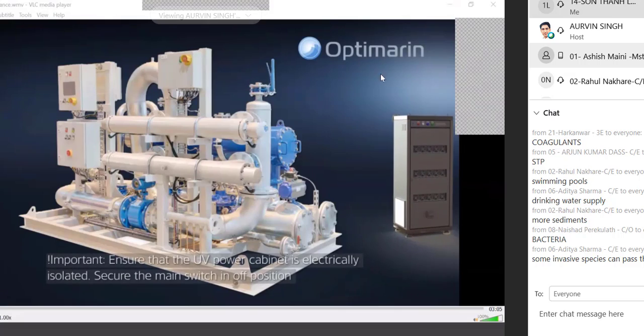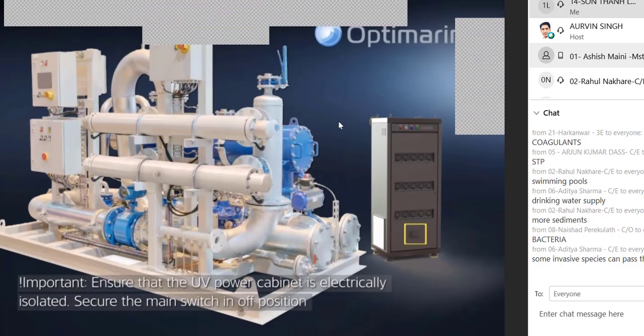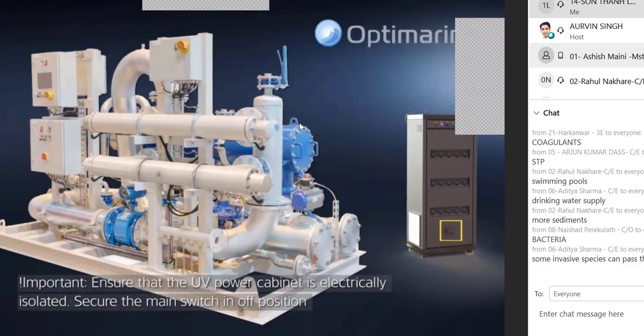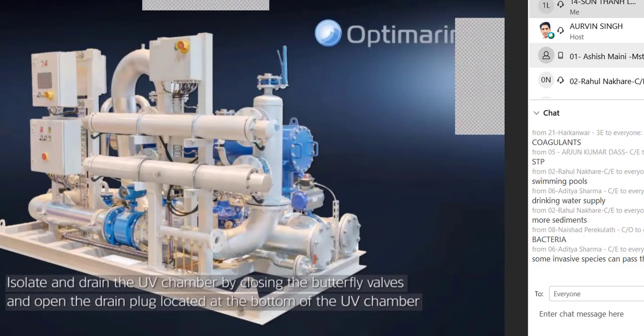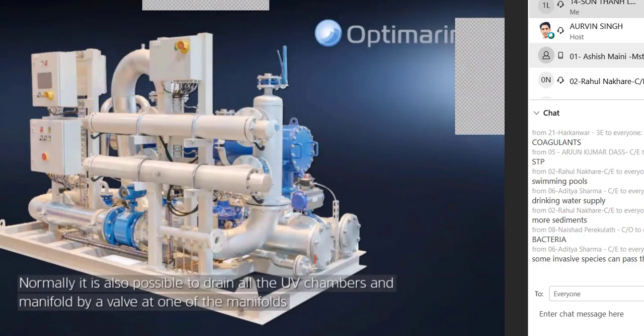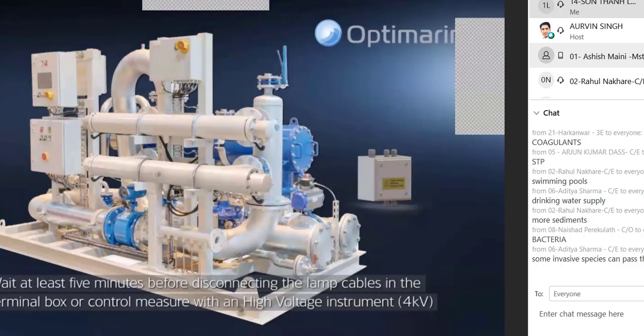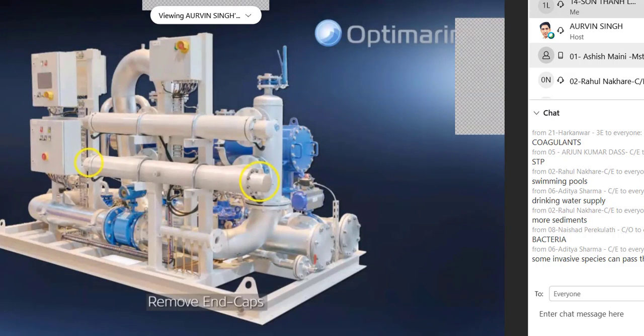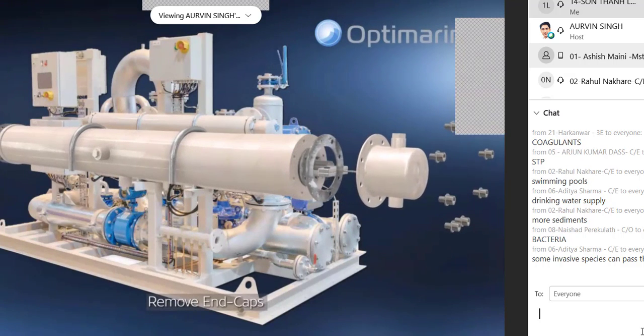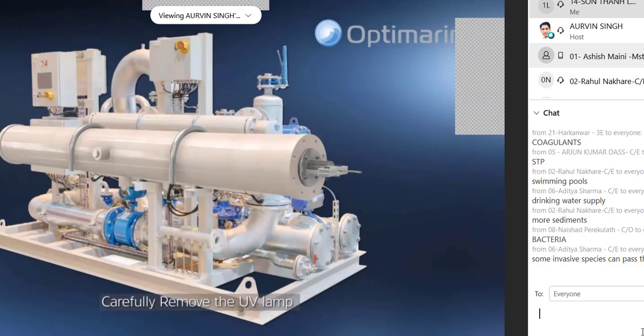Make sure that the UV power cabinet is electrically isolated. Secure the main switch in off position. Isolate and drain the UV chamber by closing the butterfly valves, and open the drain plug at the bottom of the UV chamber. It is also possible to drain all the UV chambers and manifold by a valve at one of the manifolds. Wait at least 5 minutes before disconnecting the lamp cables in the terminal box or control measure with a high voltage instrument. Remove end caps. Carefully remove the UV lamp.